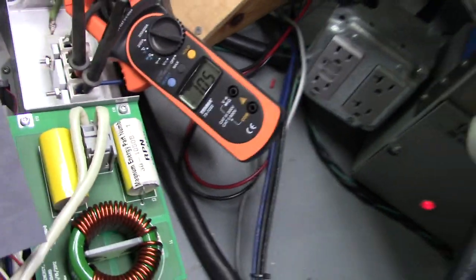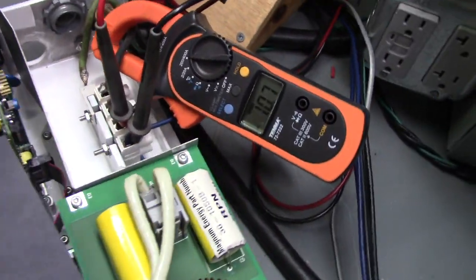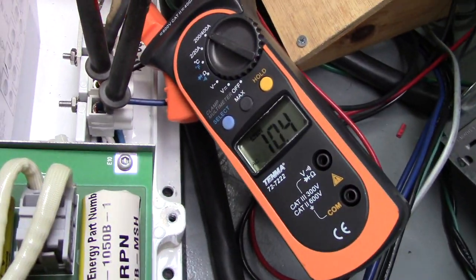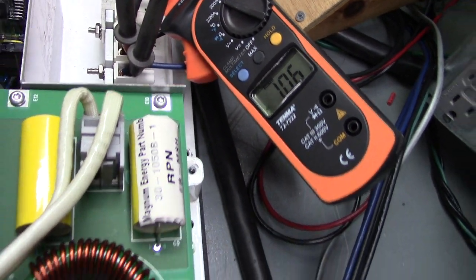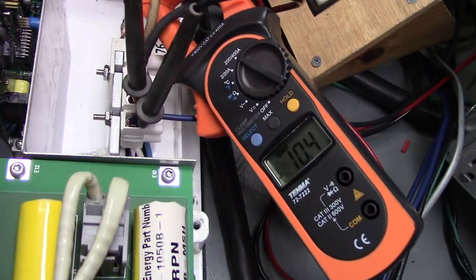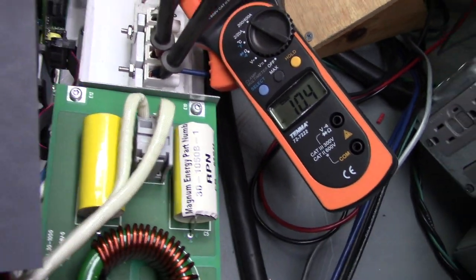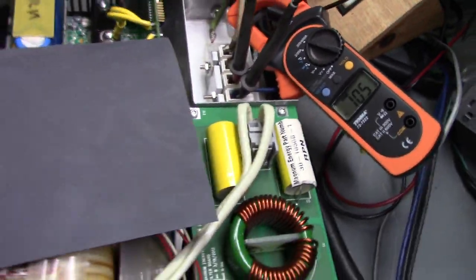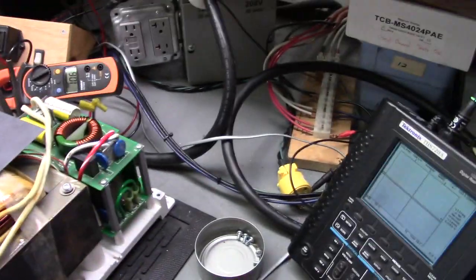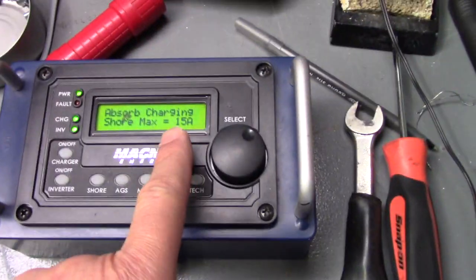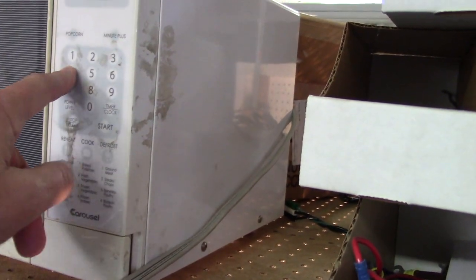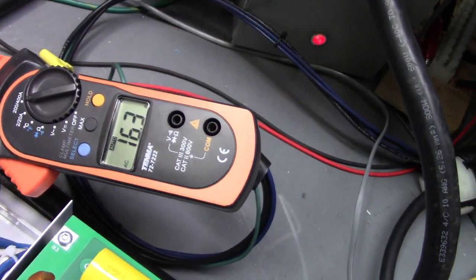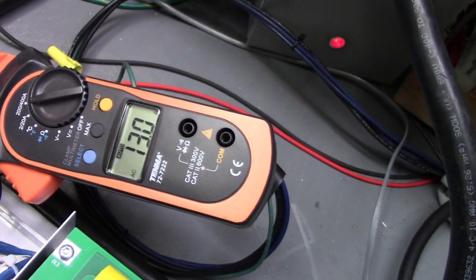Okay, so that could be, oh I don't know. You've got your TVs running. You've got some other things plugged in. Somebody's running a hair dryer. You know, I'm not sure what that would be. 10 amps might be a hair dryer. Your wife's in there in the bathroom drying her hair. So you would decide again to get up and run this microwave and you're on this 15 amp outlet. But you've got it set to 15. So let's go ahead and try to run the microwave again. So we know it's going to go over. There's 17, 16, but look at that. Right back down. It dropped down.